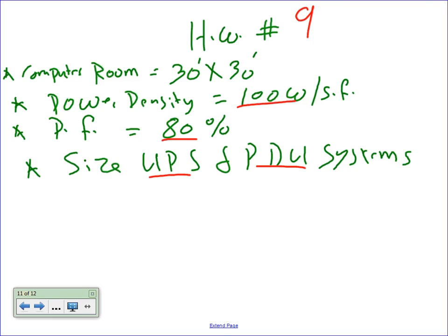Okay. I think it's 90 watt per square foot. Is that what we changed ours? Our data center is 90. The project, 90. And you take the square foot of that computer room for our project. Any questions about PDUs, UPS, and panel/transformer matching? Project is 30 watts per square foot. I think, can you guys change this one to 90? I think that's what we did. Well, he wrote down 150. Did he? Okay. Did he write 150? Okay. Let's do it. Can you guys change our project to 150? I think that's 150. The project to 150.